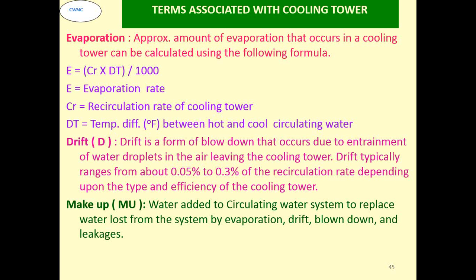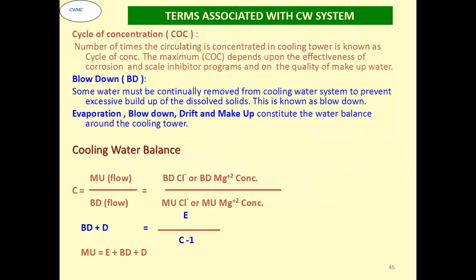That means very low. Even with a flow of about, say, 80,000 meter cube per hour, you can have only about 4 to 6 meter cube per hour as drift. Makeup water is added to the circulating water system to replace water lost from the system by evaporation, drift, etc. Cycles of concentration: suppose we have X quantity of one particular chemical on the makeup side, and in the outlet of the cooling water side it becomes 3 times X, then the cycle of concentration is 3. Blowdown is that water which we need to take out from the system so that the concentration of solids is maintained and the system is in a balanced condition. So that is the blowdown that we give.